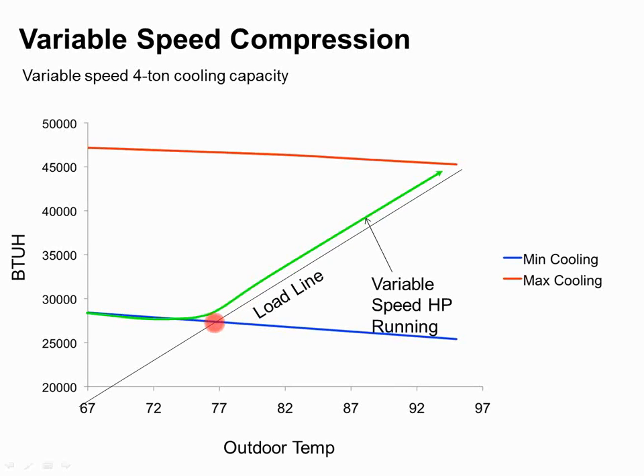So in this example, my 40% minimum. And then what I have to do is, anything below, in this case, 76 degrees, I have to shut the heat pump off and then turn it back on, off, on, off, on. But it's not off, on, going 0, 100%, 0, 100. It's going 0, 40, 0, 40, 0, 40 for these mild conditions. And in these conditions, for the most part, you're not really running your air conditioner anyway in a light commercial or residential application. Same thing happens in heating.